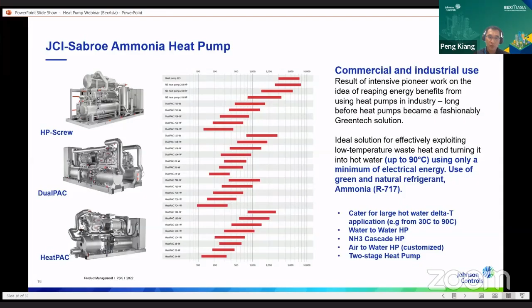One of the cases I've done is in Indonesia, right? Where we are using heat pump for laundry, CIP, and some dairy hot water requirement. So this customer has a huge amount of boiler fuel, right? That is doing boiling for pasteurization and many other things, right? And we are using about maybe 10% of that boiler fuel to make hot water from about 27 to 90 degrees C. So that translates to about maybe 308 kilowatts in terms of the heating capacity.